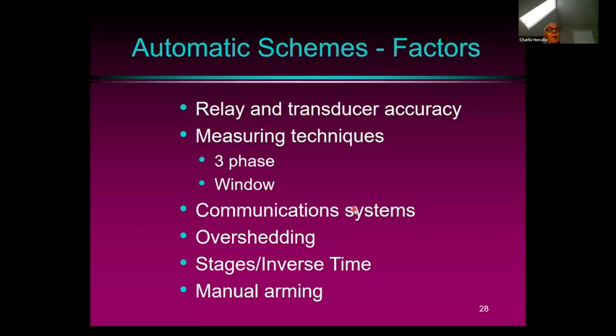Another possible problem is overshedding. So your load shedding scheme is going into service. As long as it goes in before load starts to drop off of its own free will, it needs to start operating very close to normal operating voltage levels. Otherwise, you're in danger of overshedding because your automatic scheme is working at the same time as load is just falling off the system due to low voltages.